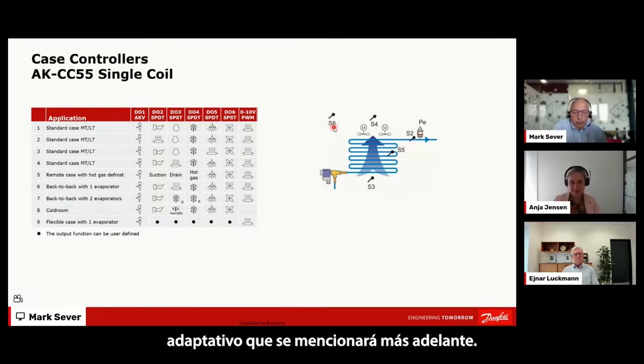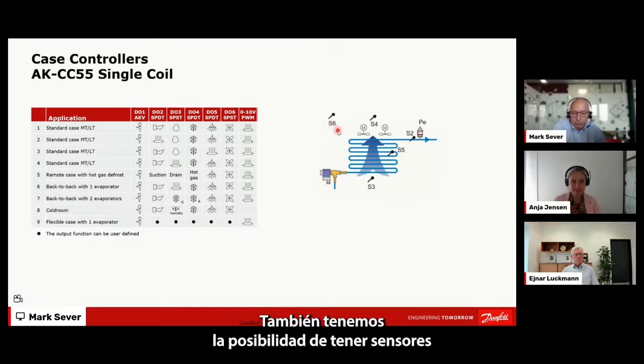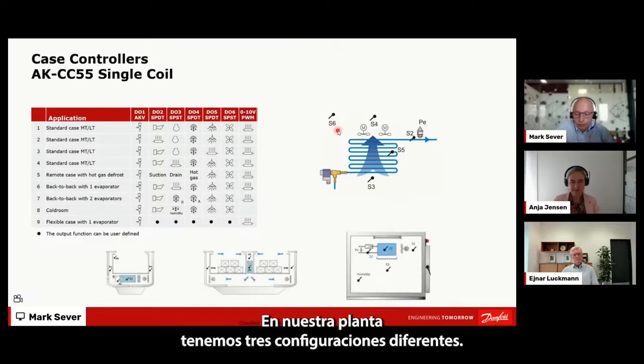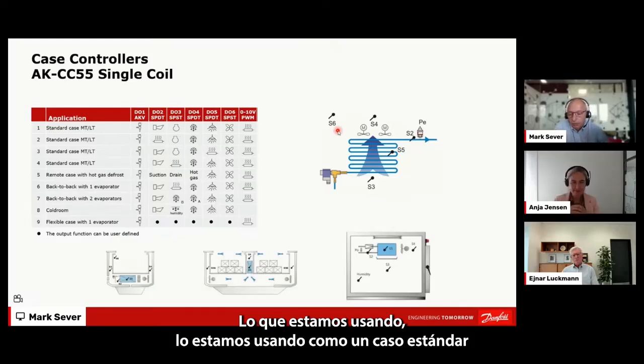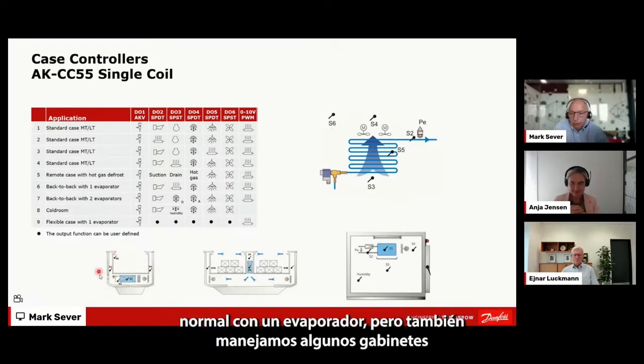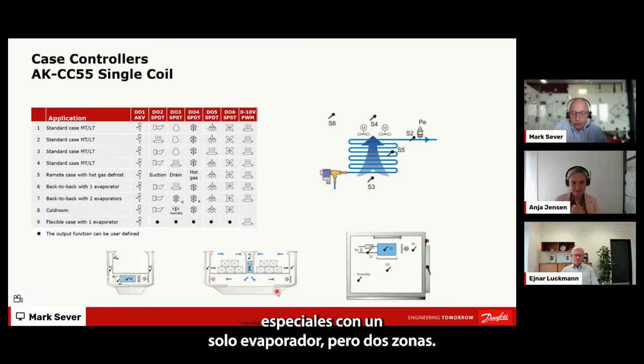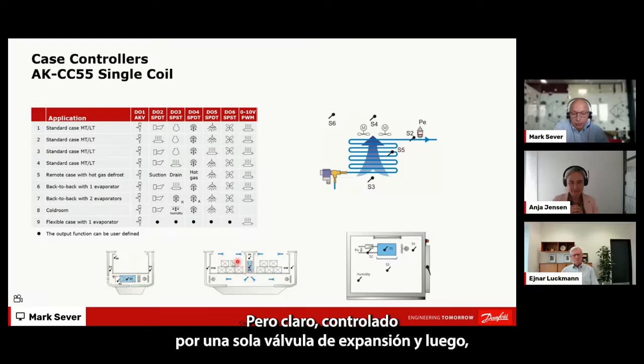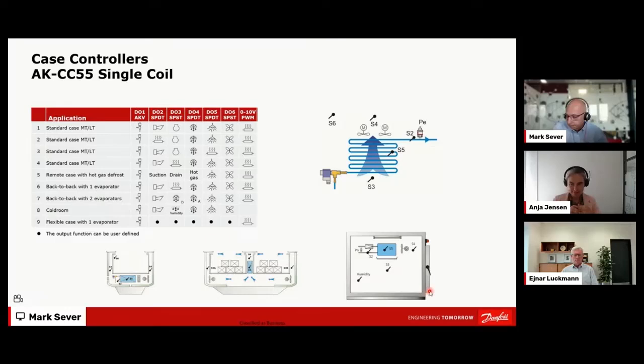We also have the possibility of an additional sensor to measure food temperature in every area you need. On our plant, we use 3 different configurations - a normal standard case with one evaporator, but also some special cabinets driven by one single evaporator but 2 areas, driven by only one electronic expansion valve. And then, of course, we have cold rooms, as I've mentioned before.